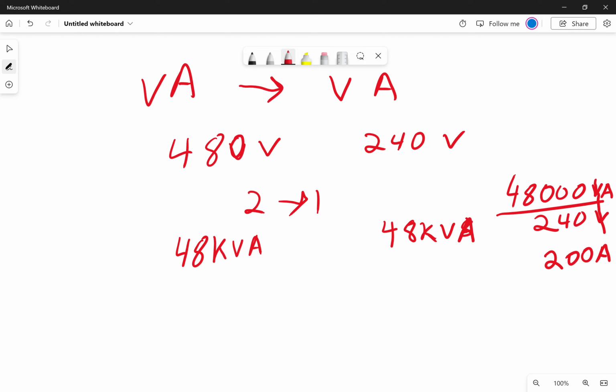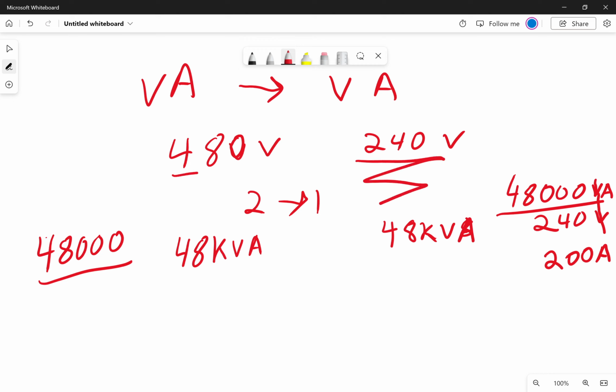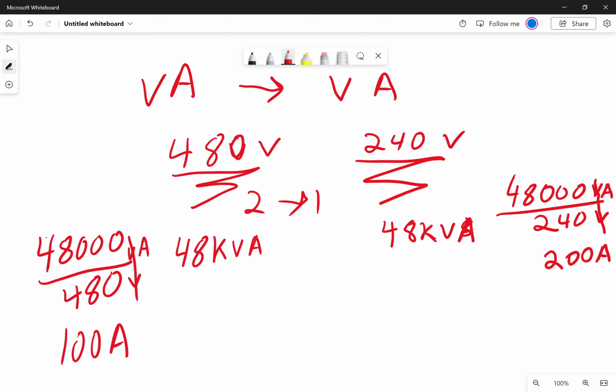For the amperage on the primary side, we do the same math: 48,000 divided by 480 instead of 240. Volt amps divided by volts, the volts cancel, and we get 100 amps. Notice our voltage cut in half, and our amperage doubled. We divided by 2, we multiplied by 2, that's how it works out.